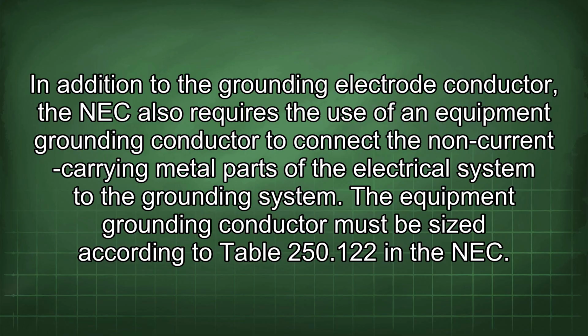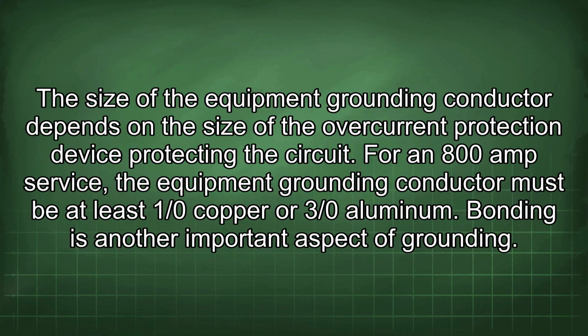The equipment grounding conductor must be sized according to Table 250.122 in the NEC. The size of the equipment grounding conductor depends on the size of the overcurrent protection device protecting the circuit. For an 800 amp service, the equipment grounding conductor must be at least 1/0 copper or 3/0 aluminum. Bonding is another important aspect of grounding.